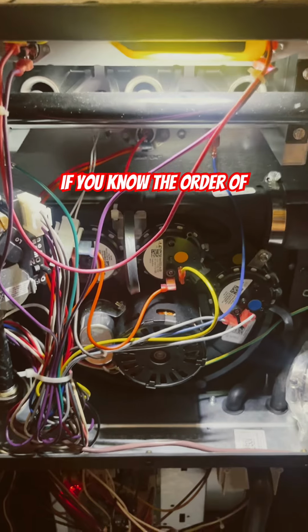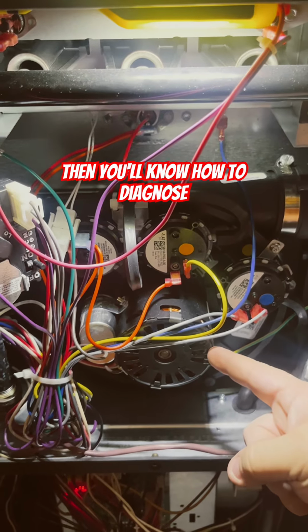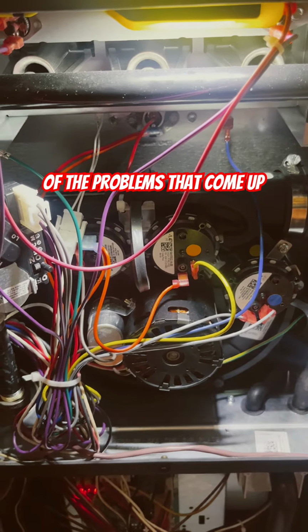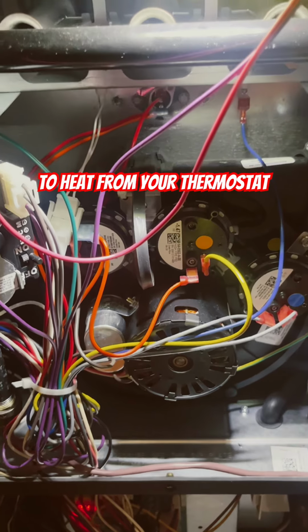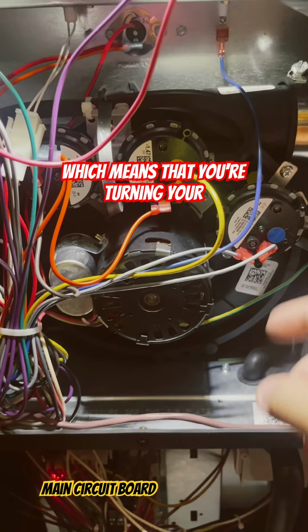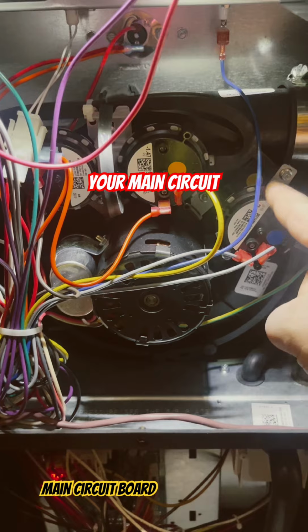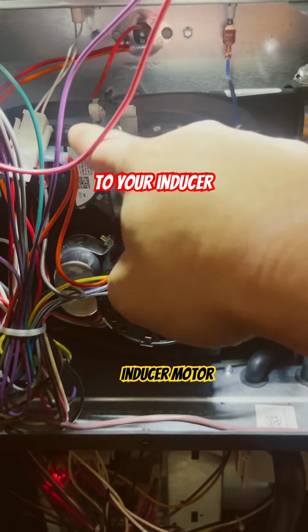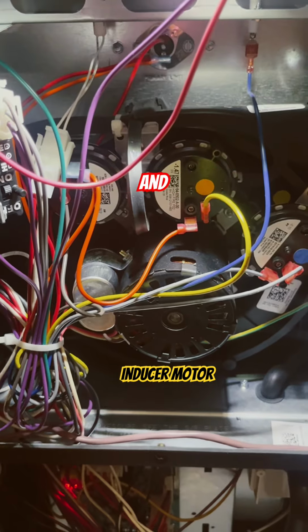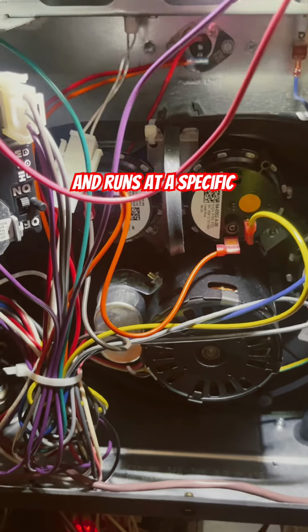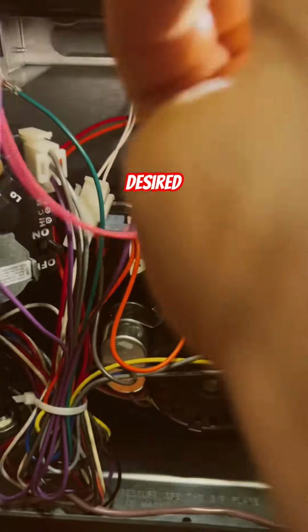If you know the order of operations of your furnace, then you'll know how to diagnose 90% of the problems that come up. It first starts with a call to heat from your thermostat, which means that you're turning your thermostat up. Your main circuit board will then send a signal to your inducer motor telling it to turn on, and when it does, it runs at a specific speed and creates the exact desired airflow for the exhaust in what's called a pre-purge cycle.